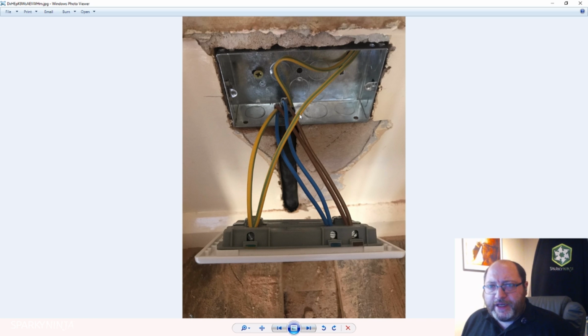I've always viewed it differently to this. I've always viewed it in what I would consider a more simple way. So bear in mind I said I do it this way. However, do you need to earth the back box? My opinion is no. The reason that the terminal is in the back box is to allow you to bring the protective conductor from the back box to the socket.